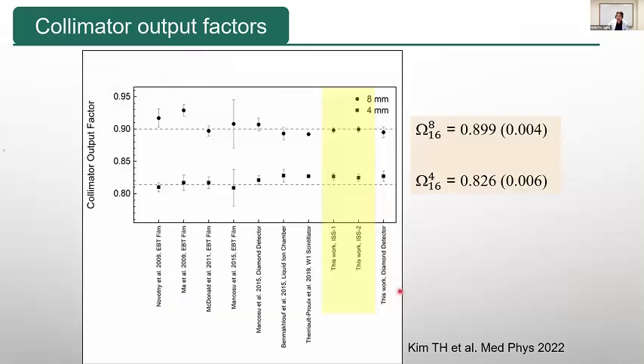Anyway. And this graph shows the collimator output factors reported from 2009 to 2022, including our work. The output factors, I didn't do this, okay. The output factor of the 8 millimeter collimator has decreased from 0.92 or 0.93 to 0.9, which is very close to the GammaPlan value of 0.9. But the output factor of the 4 millimeter collimator keeps increasing. And the recent value, 0.826 in our case, is slightly larger than the GammaPlan value, 0.814. So there might be some necessity to change these values, but it's not my work.